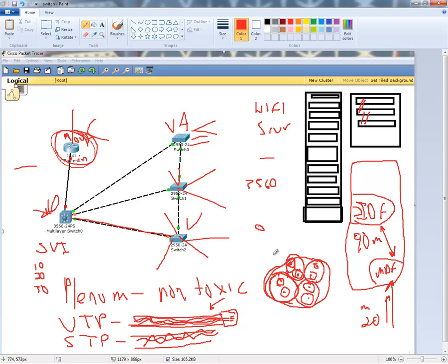So you're going to put wires where, let's say your lighting goes this way inside the building, you're going to want to run your cables parallel. If they're running through the ceiling, parallel to your lighting, not across it. And you want to make sure that you keep your wiring away from any microwaves and especially lighting. So if you have lighting running this way, you're going to want to run your cable along this wall, then to this wall, then down the wall to the floor, and then wherever it's got to go.